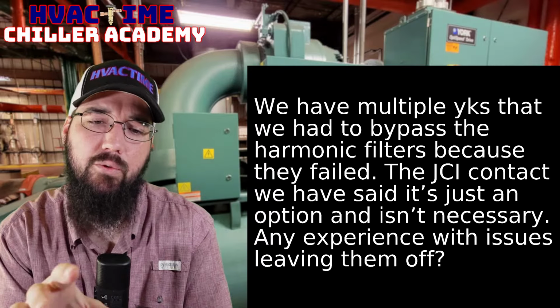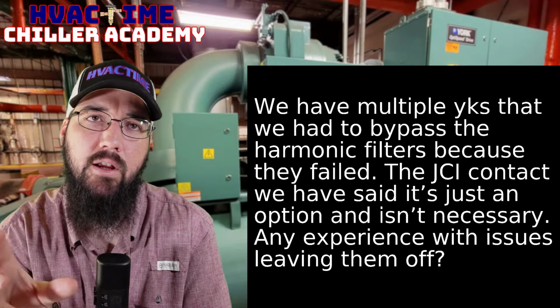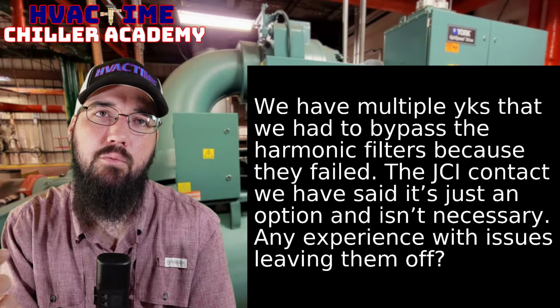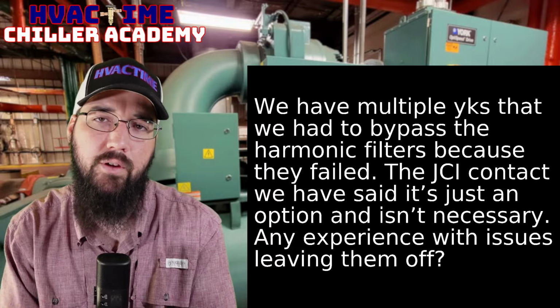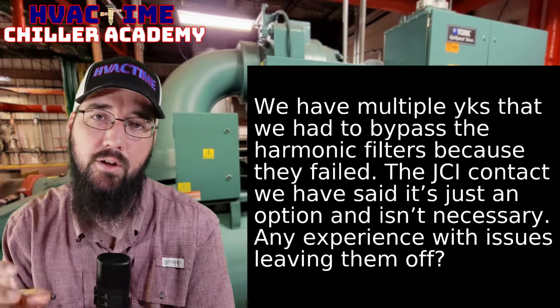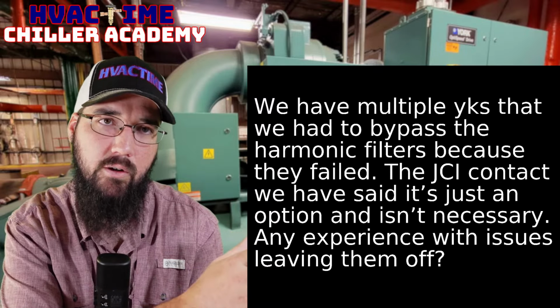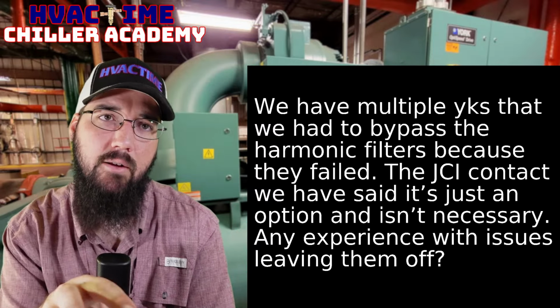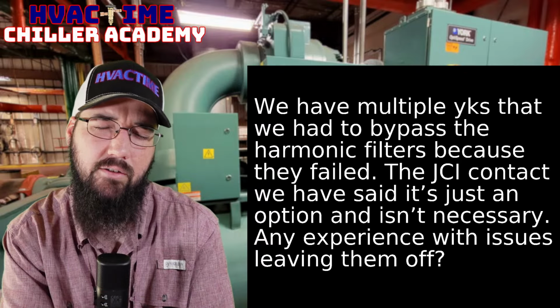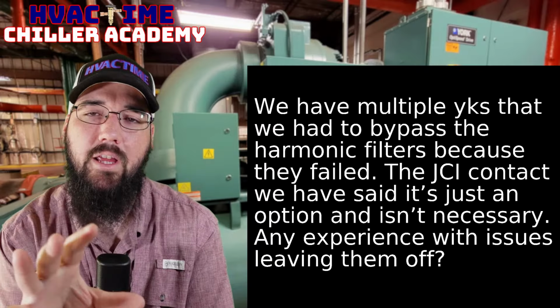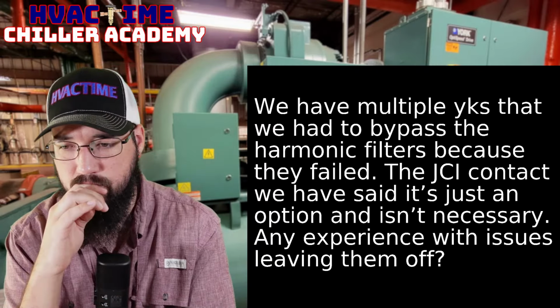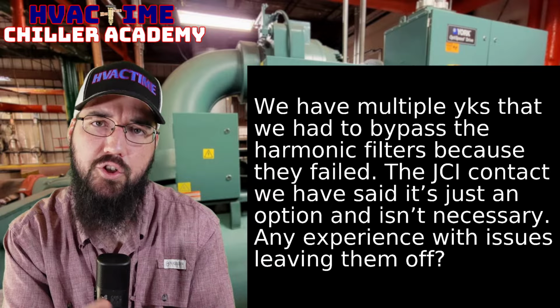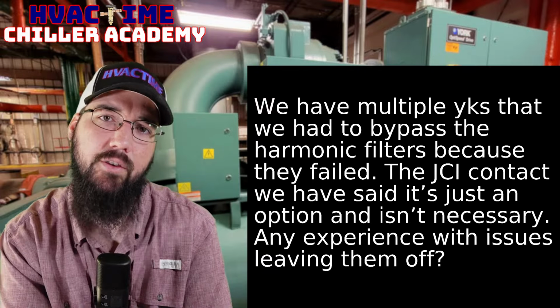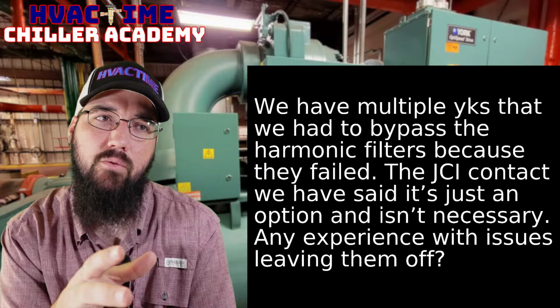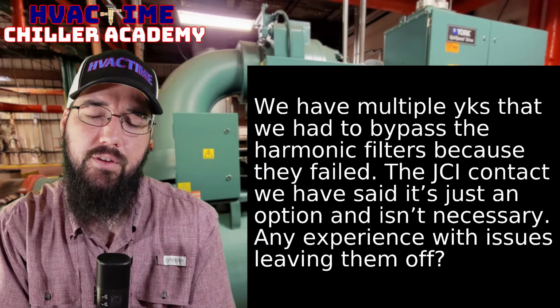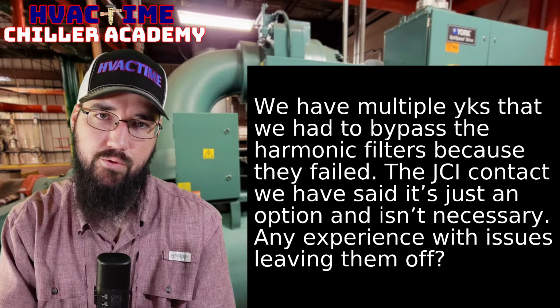And that's why they say that you can still function without the filter, because I'm assuming you're only removing the harmonic filter circuit, but you're not removing the line filter itself, which is going to be between your power input and your drive. And there are different versions of this harmonic filter. I'll get into a little more of those specifics in a minute. But keeping it to the basic version, which is what a lot of the smaller machines, let's say 1,000 tons and down, 1,000, 1,200, somewhere in there, use, it wasn't necessary, like they told you, it was an option.